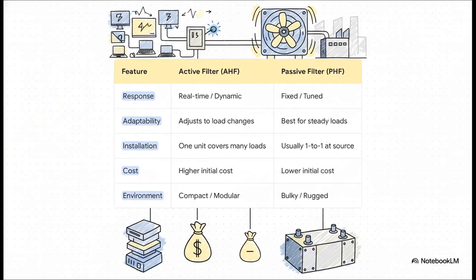What's really fascinating here is the trade-off. Active filters are dynamic. They can adapt as the electrical load changes, which is perfect for a modern office where people are turning computers on and off all day. Passive filters, on the other hand, are best for really steady, predictable loads, like a giant fan in a factory that just runs 24/7. Active filters cost more up front, but one single unit can protect an entire electrical panel. Passive filters are cheaper, but you often need to install one for each problem machine.